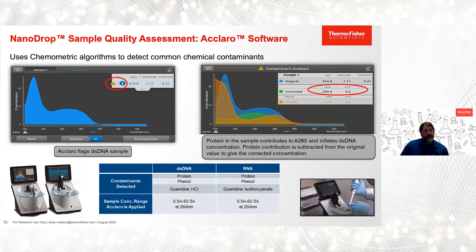After years of training customers how to read this full spectral data, we realized we could use chemometric algorithms to give our customers a clearer picture of the type and amount of contamination present. In the past eight years, we've introduced chemometric algorithms we call our Acclaro software into our NanoDrop devices, specifically the NanoDrop One and the NanoDrop Eight models. This feature now flags potential contamination and also gives an accurate, corrected concentration by removing that contaminant spectrum. Our detection scope currently encompasses protein, phenol, guanidine salts, and mammalian RNA.